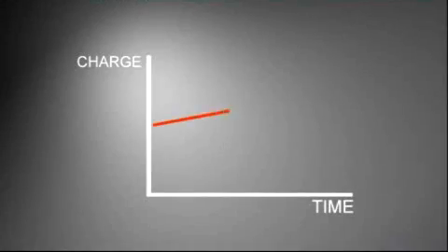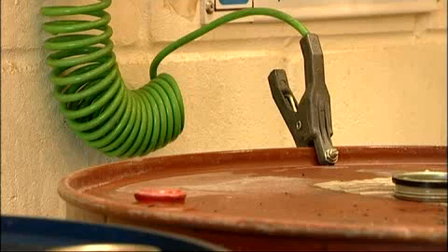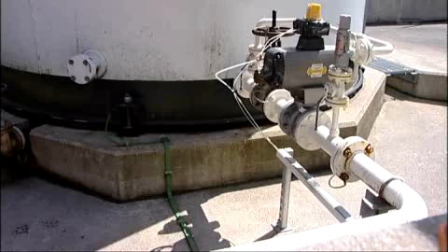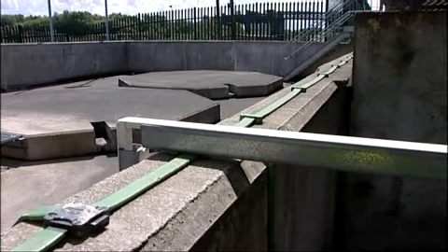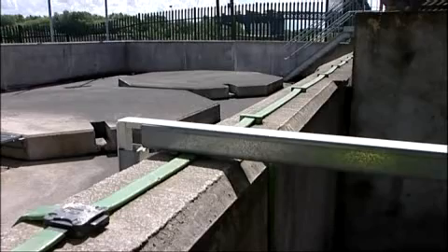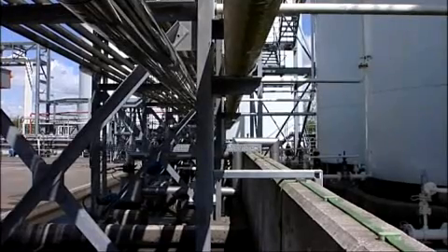Earthing establishes a continuous electrical path to earth and will remove charge rapidly. Conductive equipment is connected to an earthing electrode or to the building earthing system in order to prevent sparking between conductive equipment and earthed structures. A bonding system connects various pieces of conducting equipment together to keep them at the same potential. Static sparking cannot take place between objects that are at the same potential.